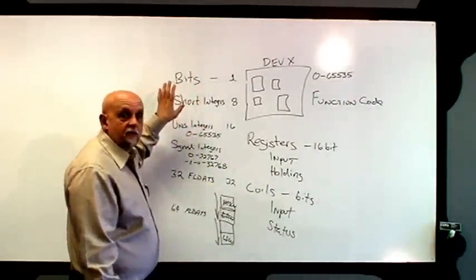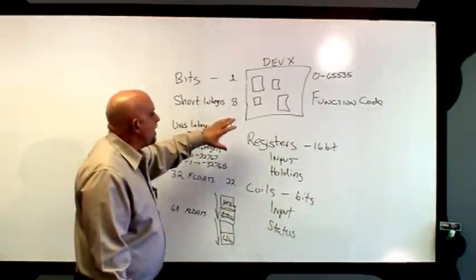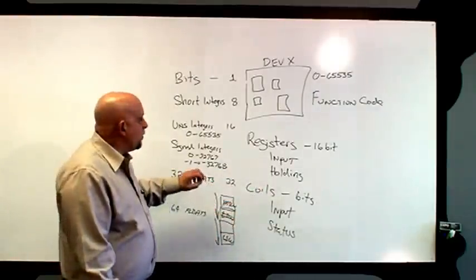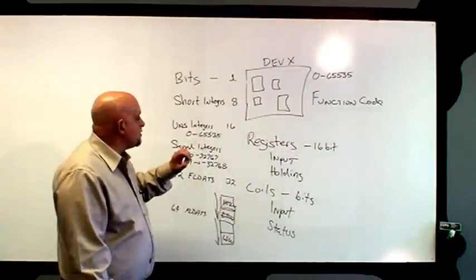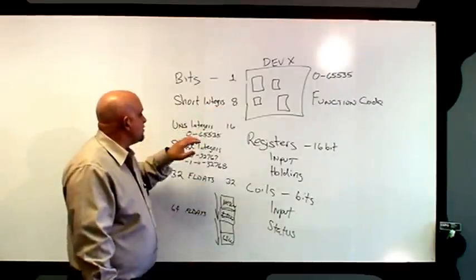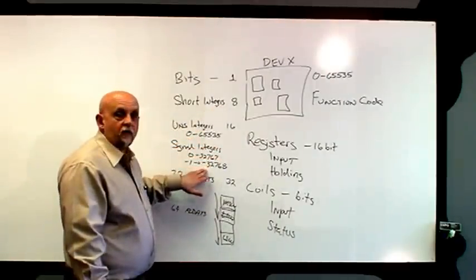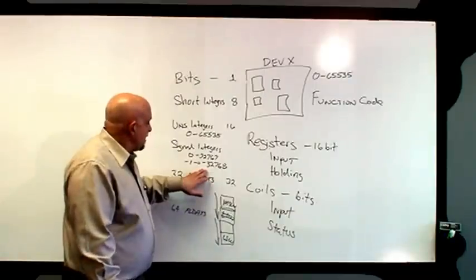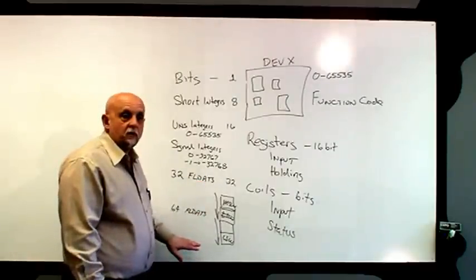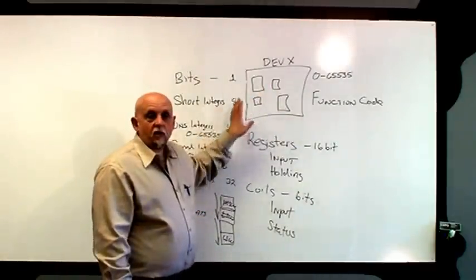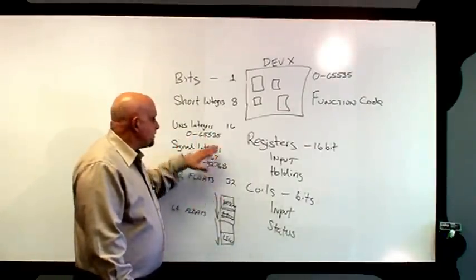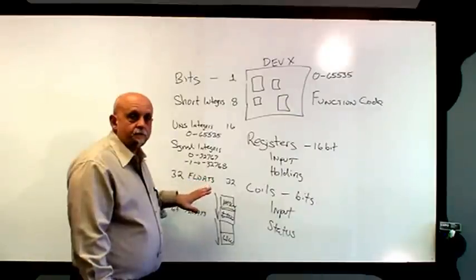You can support lots of different data types — and these are just the standard ones, there are lots of others — even though Modbus only defines registers and coils. When you pull data out of the Modbus register, you can map a short integer into another computer's data memory where it recognizes short integers, map a signed integer value into a data table entry that recognizes signed integers, and the same with floats. Within the Modbus structure, they're still individual single registers comprising all these different data types.